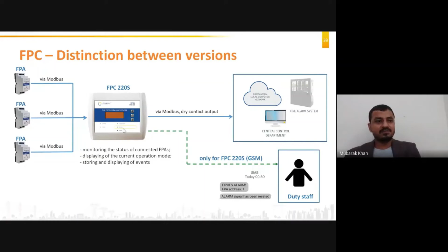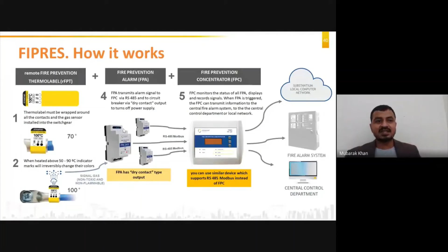So this is a complete system configuration, where RFPT is the remote fire prevention thermolabel. RFPTs will be installed on the contact connection points or parts of electrical equipment which are potentially prone to overheating. It will be placed very near to the joint so that it can work at nearly the same temperature as the joint. When the joints get overheated, a signal gas will be emitted from the sticker, which will fill the compartment with a particular gas concentration. Then we have a device known as FPA, which will be placed in the same compartment, which will sense the presence of the gas and give you a remote alarm directly or through FPC.